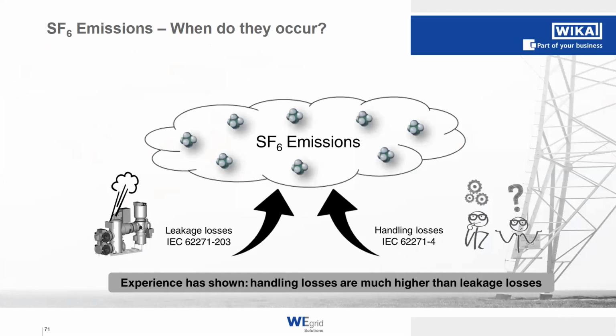So when do SF6 emissions usually occur? We have the technical side, the leakage losses, which are described in the IEC norm, and then we have the handling losses. Leakage losses involve technical failures, like a valve that is not functioning anymore, and handling losses would be insufficiently connecting the hose to the gas compartment, or damaging the gas compartment connection while plugging the hose onto it. Those are all handling losses, or just overfilling, for example. And our experience has shown that handling losses are much higher than leakage losses.